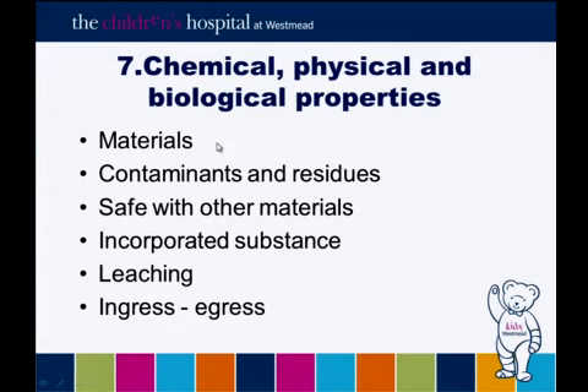So you've got to look at the materials you build it from. That's the biocompatibility. You've got to look at contaminants and residues. When you're plastic moulding, there's a lot of stuff, release agents and stuff, that can stay on the surface that aren't particularly biocompatible. You've got to show that it's safe with other material. One of the big problems with metal implants originally was they were never quite made out of the same type of steel, so you got galvanic action if you put them too close to each other.